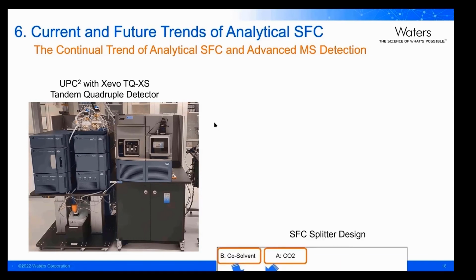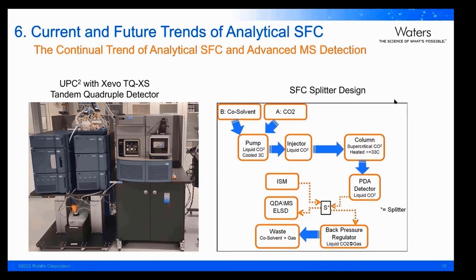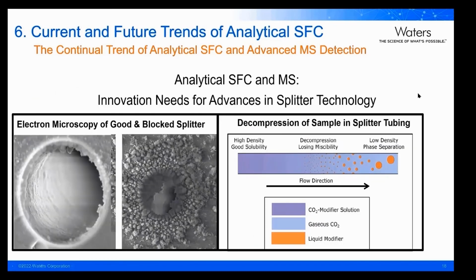Analytical SFC coupled with mass detection does require a splitter, and that splitter needs to be specifically designed to account for carbon dioxide and the desolvation of the carbon dioxide as it goes through the splitter. This is a technology that probably needs to be advanced more as we get into the higher, more sensitive mass detectors. Some of the science and technology that needs to be developed is how to account for splitters that do get blocked because of particles desolvating in the splitter and the decompression of the sample in the splitter tubing.